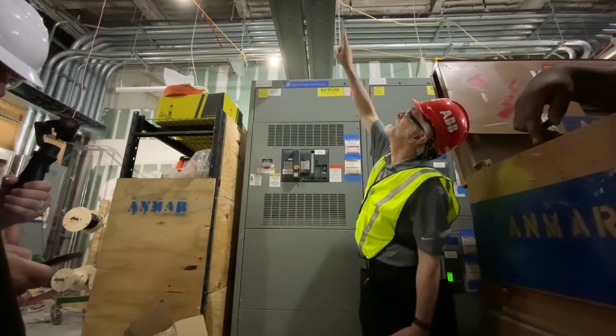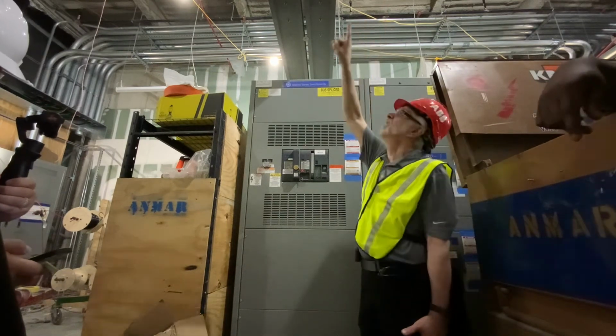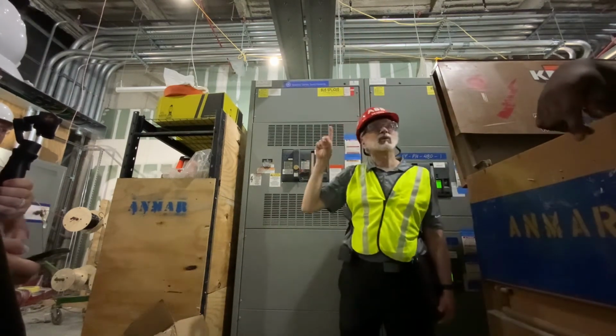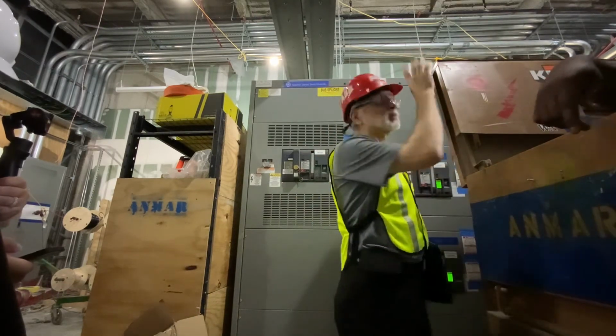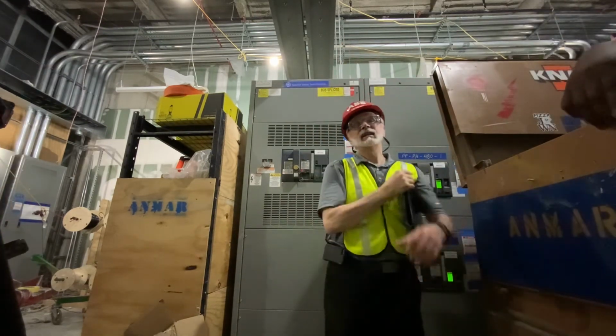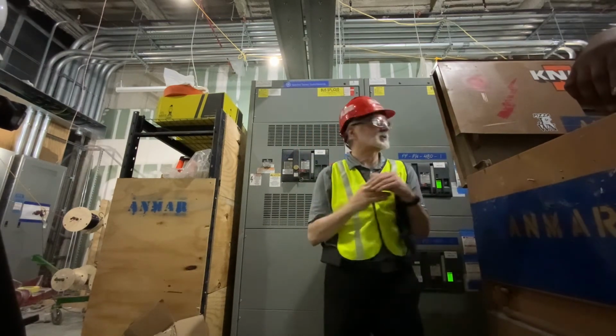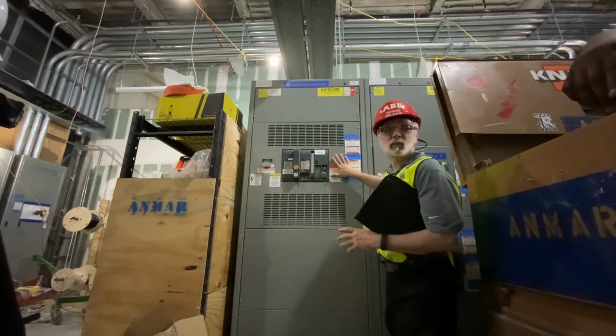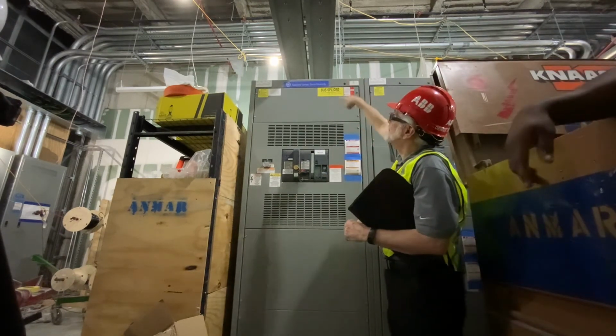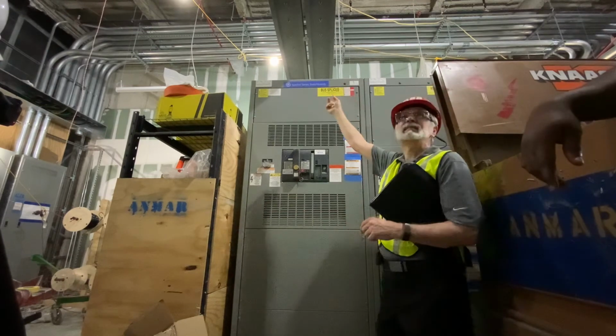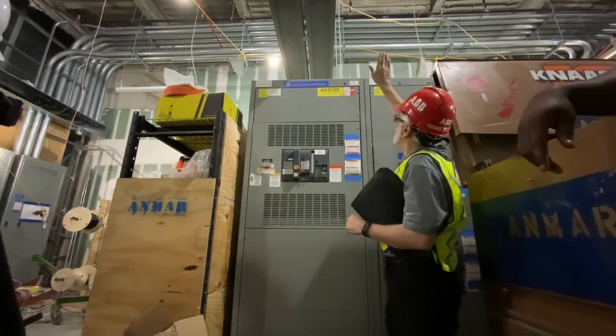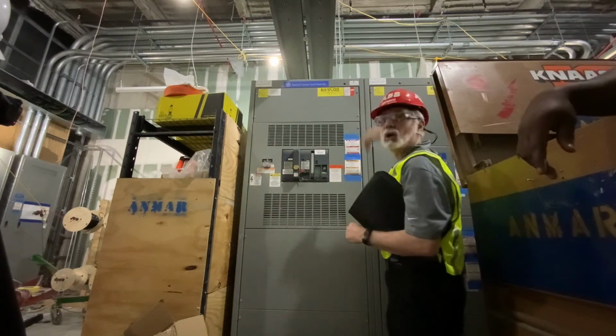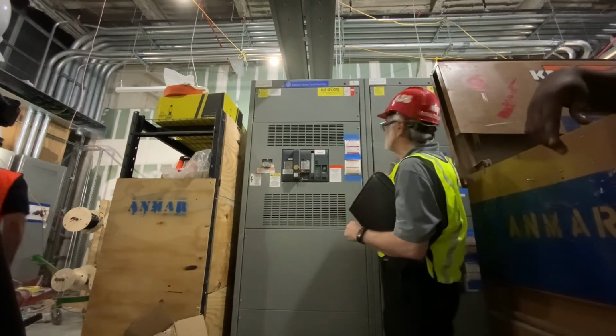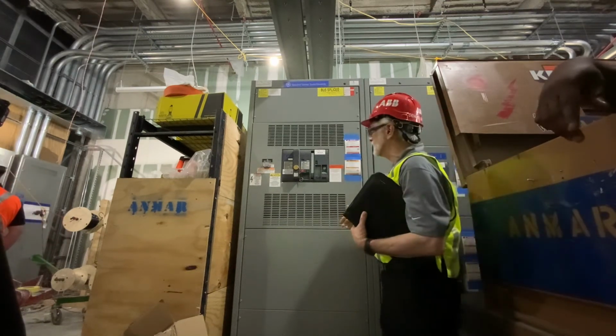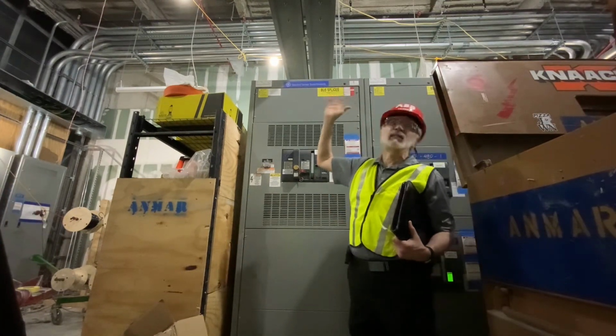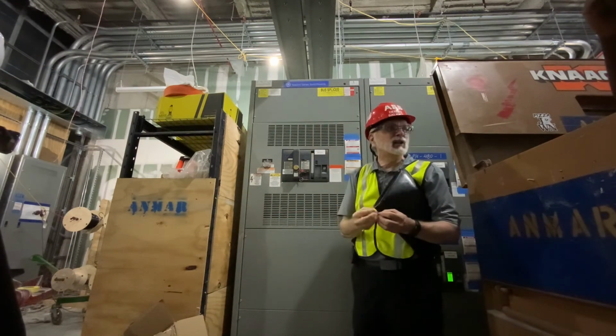You can see here is the busway that is connecting the 2 pieces of equipment. This busway is the same busway that runs throughout the building vertically to give power to each one of the floors. So you would have a large circuit breaker like this, with a piece of busway coming out, but instead of going over to another piece of equipment, it would probably go out the back and down to service another floor, and it would probably say busway 1, or busway 1, 2, or something like that.